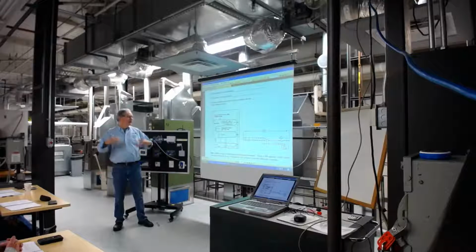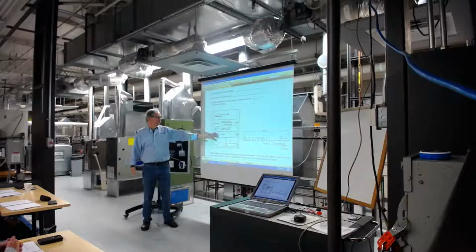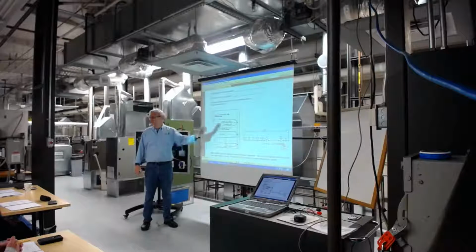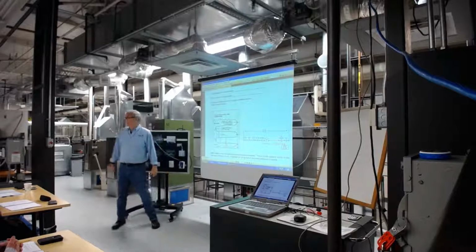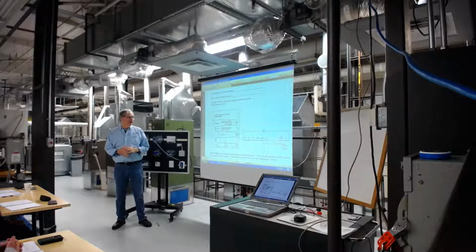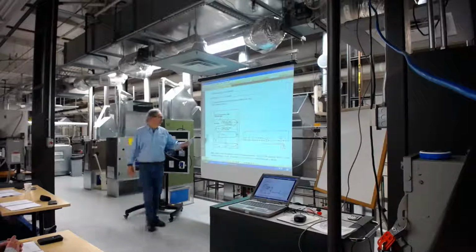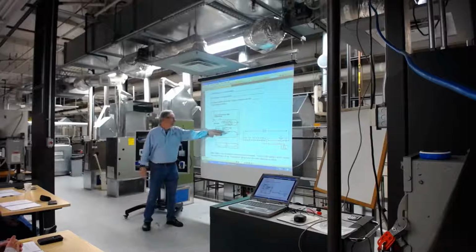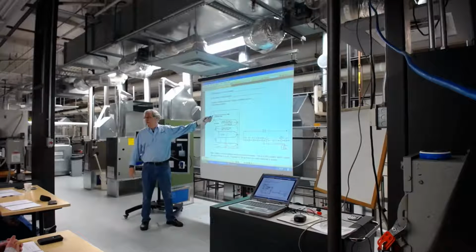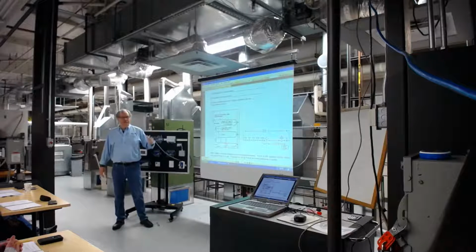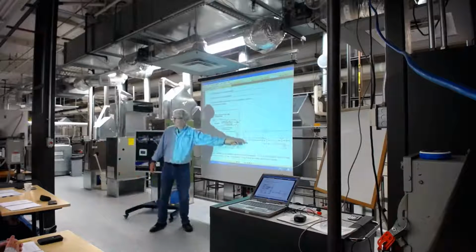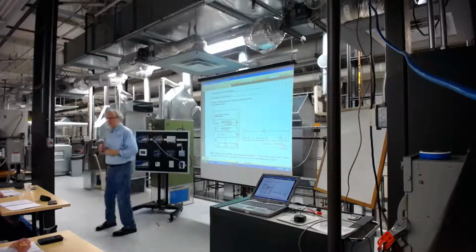So the idea is, if you get below a certain temperature, it's going to shut the whole system down. That's what they're saying, so we're going to try to protect it. What would happen is the dampers would close, the fan would go off, and all that kind of stuff. So what happens is you've got this capillary. Right here is a set of contacts. The electrician then will wire those in series with the starter, which is right over here. Okay. That's the whole idea.